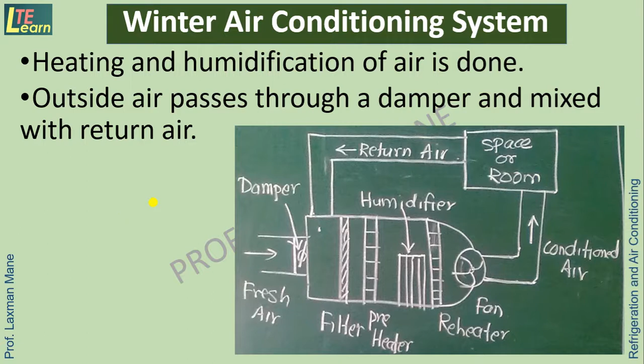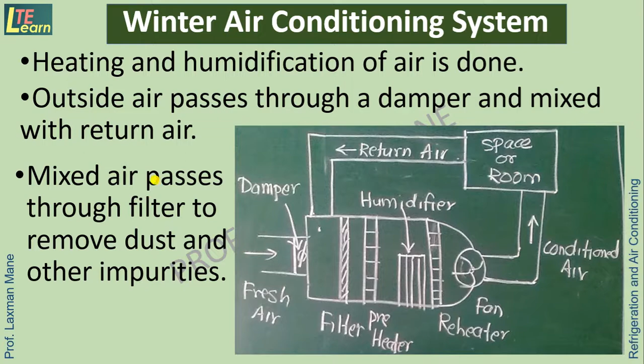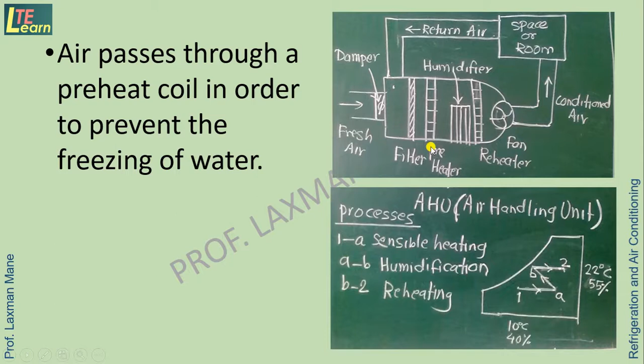Outside air passes through a damper and mixes with return air. This mixed air then passes through filter in order to remove dust and other impurities. Then air passes through a preheat coil in order to prevent the freezing of water. Then air passes through reheat coil to bring that air to designed desirable temperature.